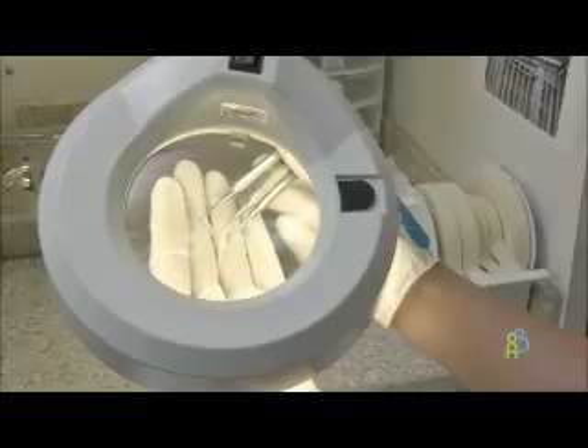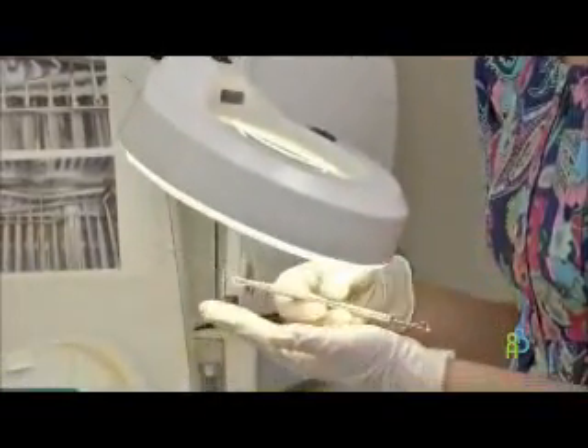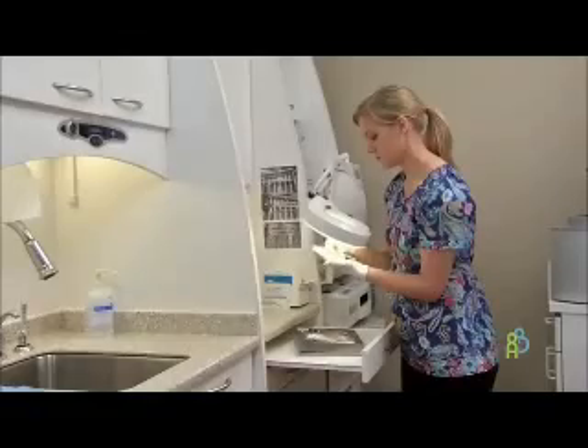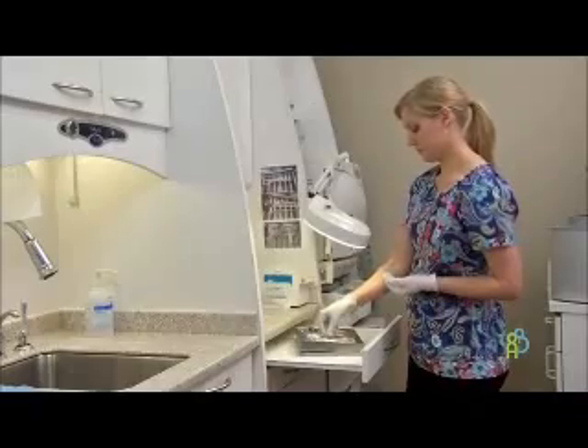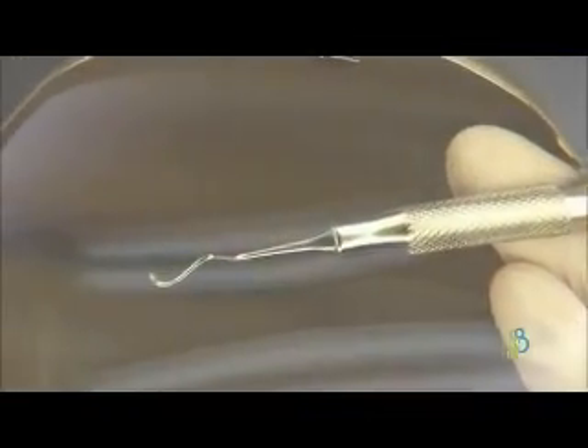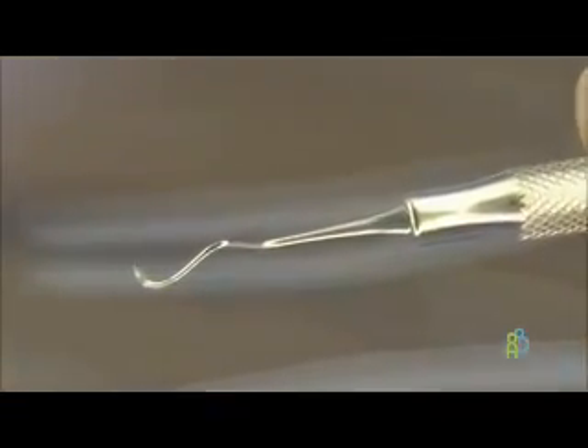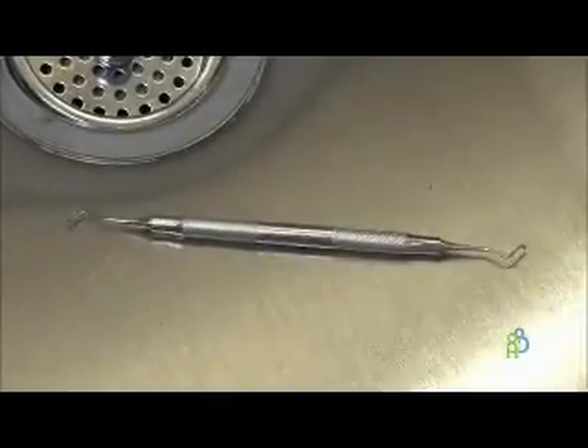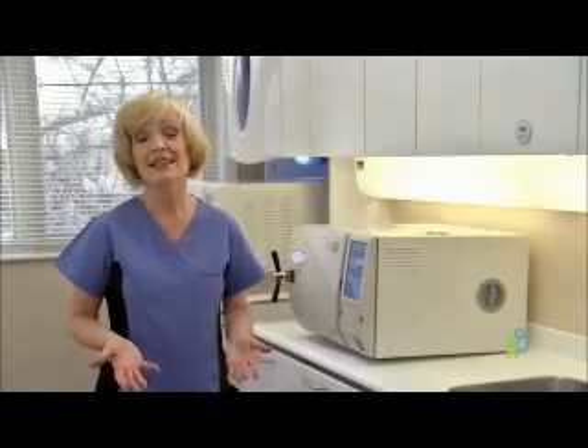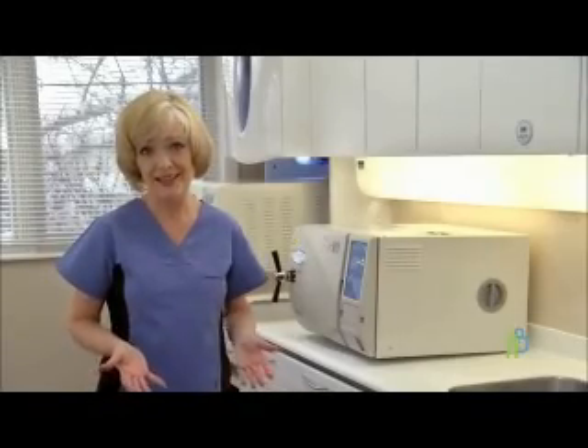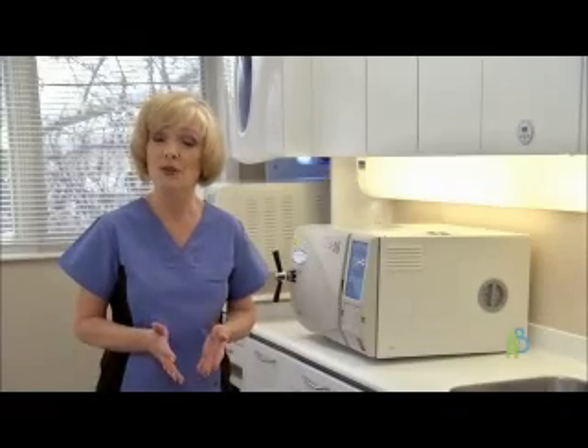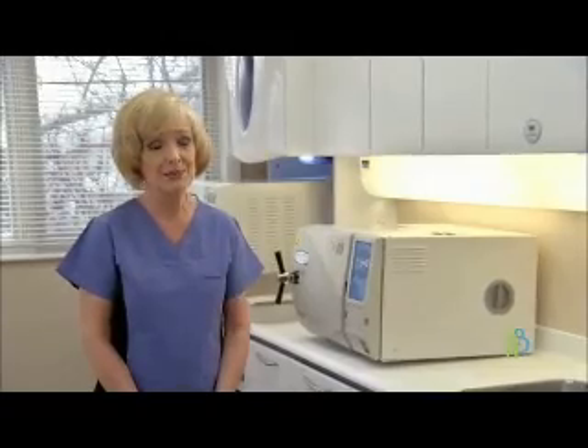Devices are inspected for cleanliness, functionality, and integrity. If the instrument is not clean, the cleaning process must be repeated. If defects are noted, the instrument must be removed from service and either repaired or replaced. Drying is an essential step in reprocessing as it prevents microbial growth and protects instruments from staining and corrosion resulting from exposure to minerals in tap water.